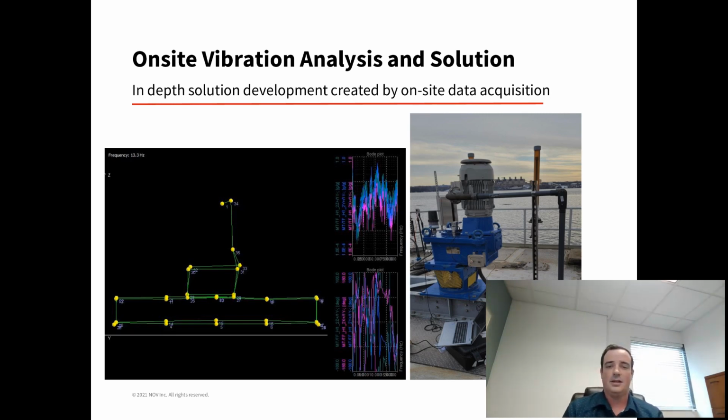What modal analysis entails is impact testing, or testing for natural frequencies. We have calibrated equipment to impact a piece of equipment and see what the natural frequency is. We also can do an operational deflection shape. Now, that's what's animated or going to be shown here shortly. An operational deflection shape is real-time operation of the equipment with data gathered at many points. We take all this data and we can then animate it and show people what is going on at specific frequencies or throughout the whole broad spectrum of operation. I'm going to pause here quickly and show you an animation, or what it actually looks like.